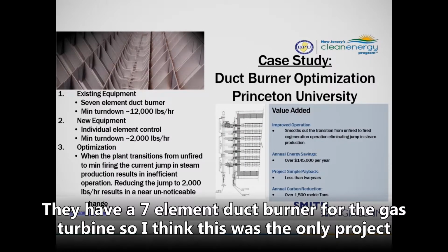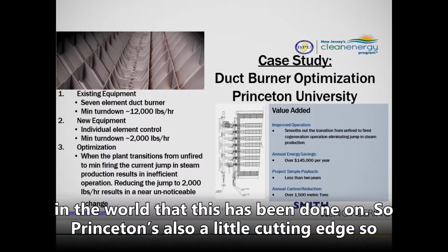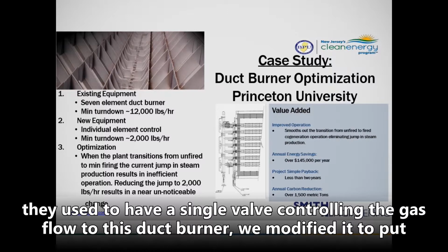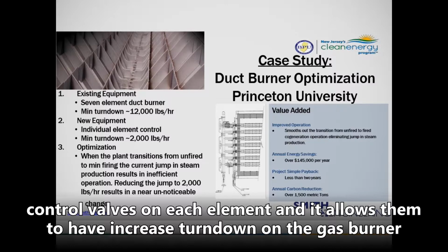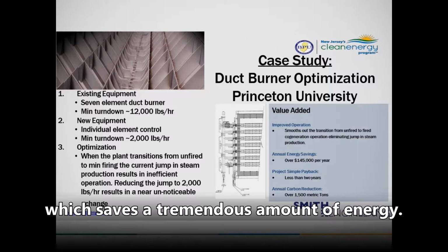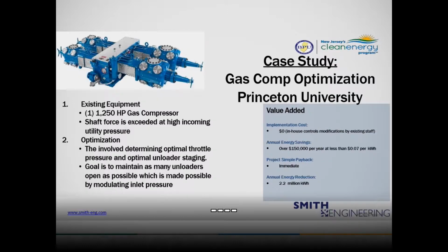They have a 7-element duct burner for the gas turbine. So I think this is the only project in the world that this has been done on. So Princeton's also a little cutting edge. They used to have a single valve controlling the gas flow to this duct burner. We modified it to put control valves on each element, and it allows them to have increased turn down on the gas burner, which saves a tremendous amount of energy.